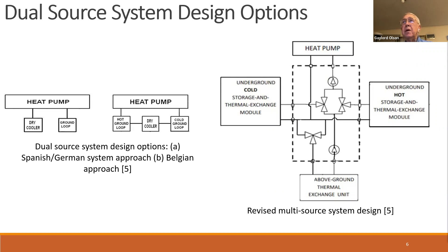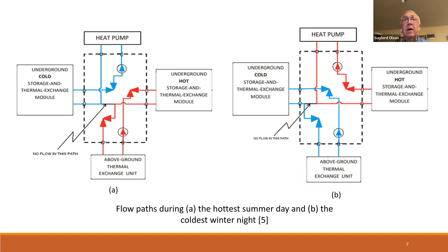So this shows the flow paths for the preconditioning capabilities of that design. Red for hot, blue for cold. So the left hand shows the valve settings for preconditioning for heat into the right hand bore field, and getting nice cold water for the heat pump. So you have high efficiency. And the opposite season is on the right, of course. And this is the coldest winter night. And you're putting really cold water into the left-hand bore field and getting nice warm water from the right-hand one. So this is equivalent to what was proposed by the authors in Belgium. So going on, yeah.